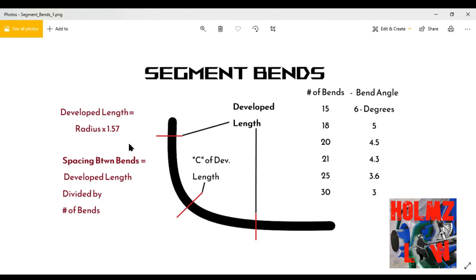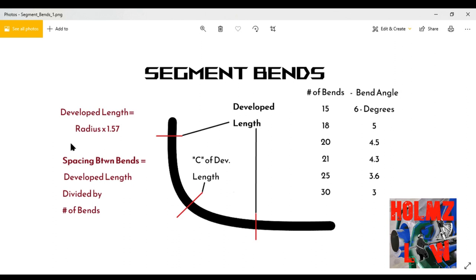Let's get started. We're going to start with the developed length. If you look here on the screen, we're going to store the multiplier — it's going to be 1.57. You take the radius and times it by 1.57, and it's going to give you the developed length. Up at the top you can see the formula: developed length equals radius times 1.57.